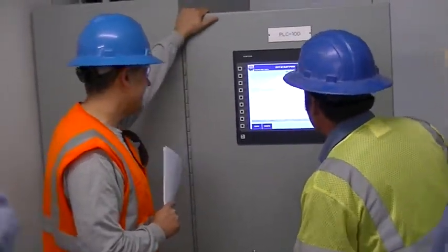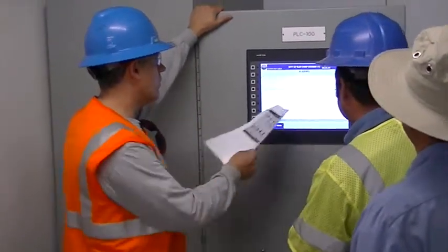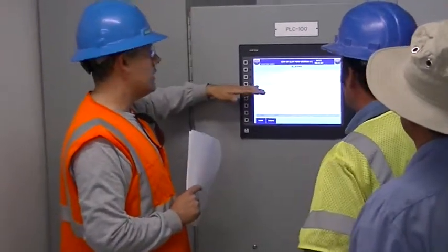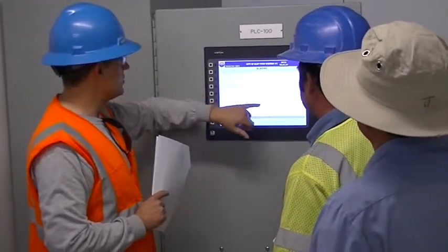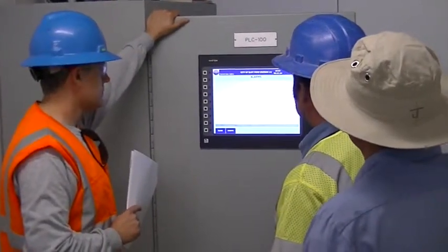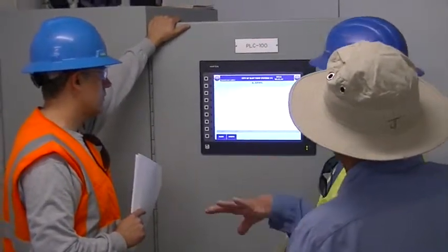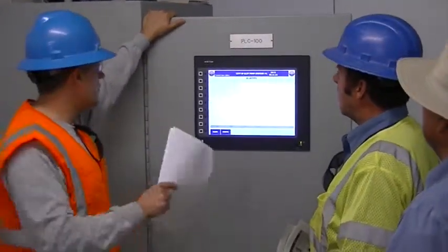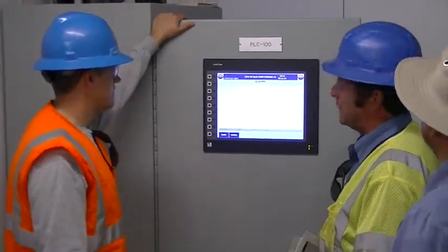There you go. Now, if it's a current one, though, it's not going to change to green, right? No, it won't change to green until it's cleared. Okay. So if it's active and then it clears itself, it'll turn green. If it's still active, but you hit accept, it'll turn olive. Right. Okay. It had turned green for a minute, but the intrusion alarm, is that just in this building? You have the 3 doors with intrusion alarms, and then you have a cabinet intrusion alarm as well. And that's this one right here. Right. All right.